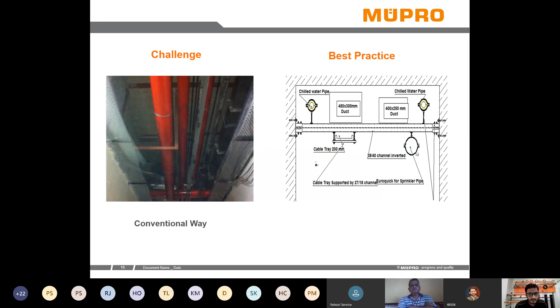Now this is another challenge which we face in our day-to-day installations through the conventional system. Here they have tried to make a kind of thrust block and a supporting arrangement bracket. These two supports can be combined in a single support with fewer anchor fasteners. Another thing is, such a system doesn't give you flexibility of adjusting the length of the pipe from the wall. You cannot move this pipe nearer to the wall or away from the wall once this support is installed. It is permanently fixed.